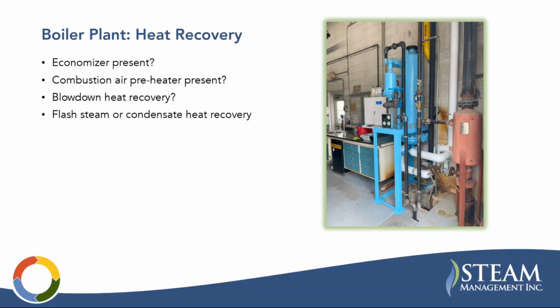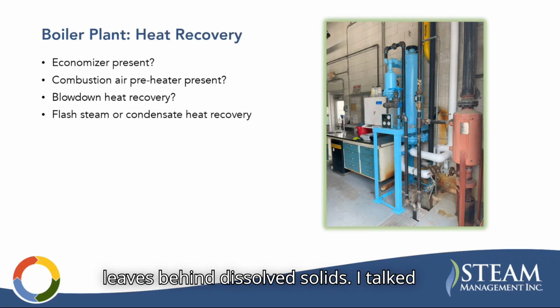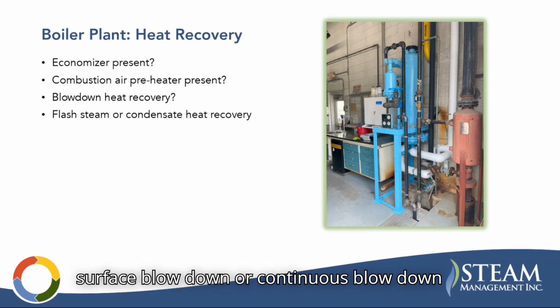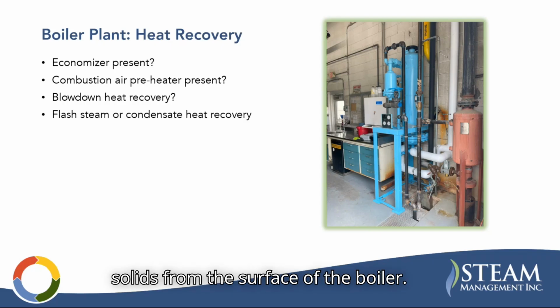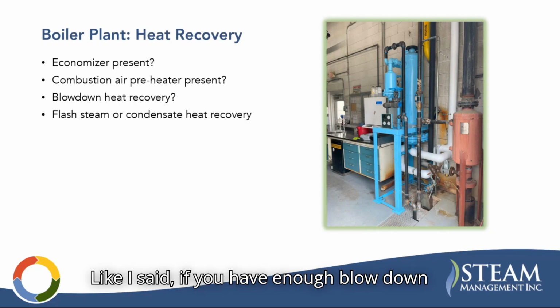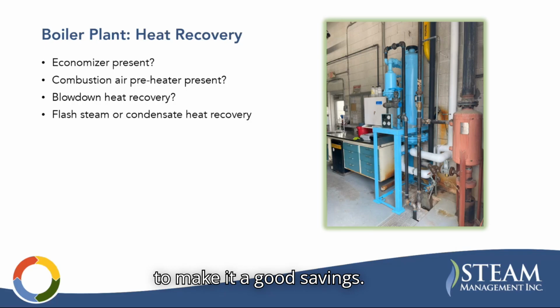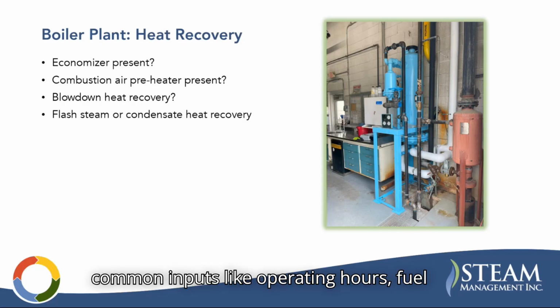Some other heat recovery opportunities: blowdown heat recovery. As steam evaporates in a boiler, it leaves behind dissolved solids. I talked about this in other webinars, so I won't go too far into it, but basically you have a stream of surface blowdown, or continuous blowdown, out of the boiler that removes these solids. That's just a wasted stream of saturated water. You're heating that water all the way up to boiler pressure and temperature, and then you're rejecting it down the drain. So you can recover heat from that, and you can recover flash steam from that. It's a great opportunity, like I said, if you have enough blowdown to make it a good savings. That's often driven by the water quality, as well as other common inputs like operating hours, fuel costs, and water costs.